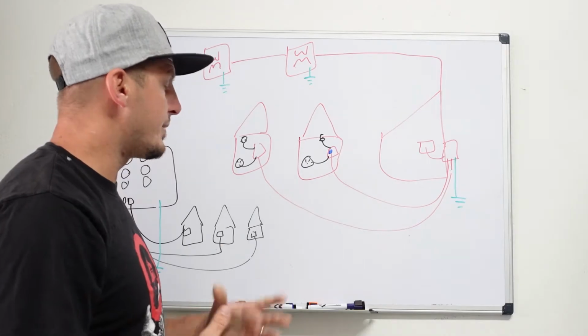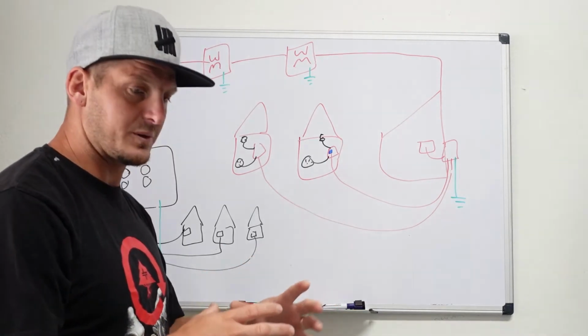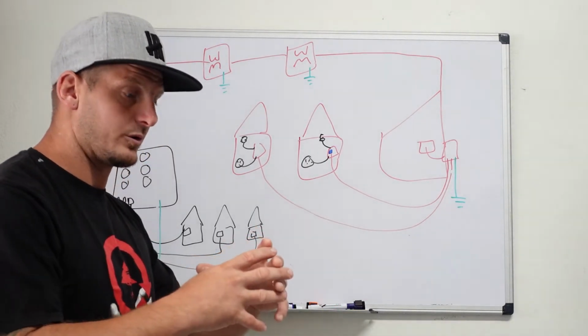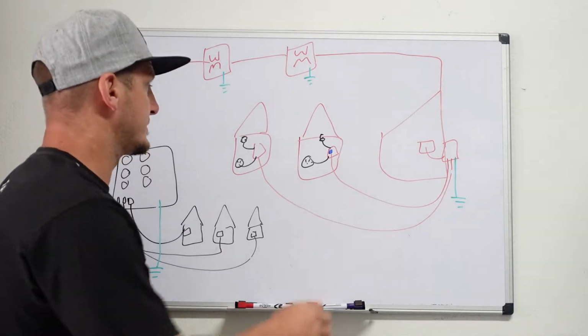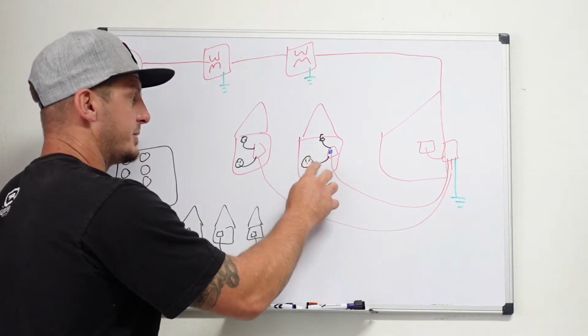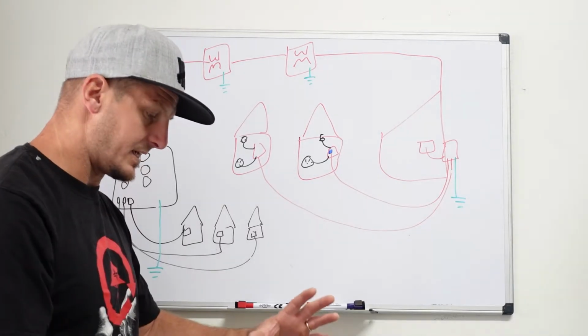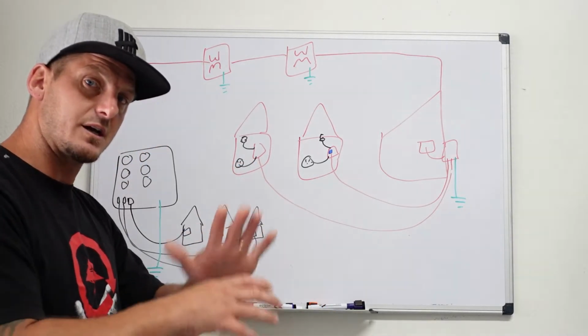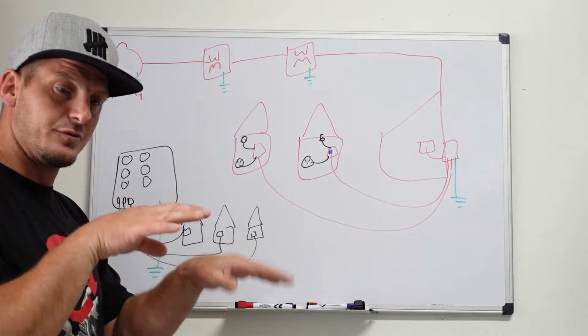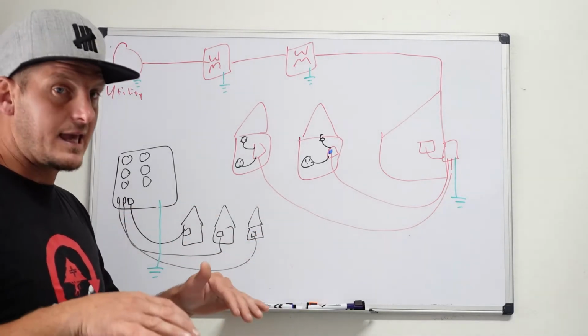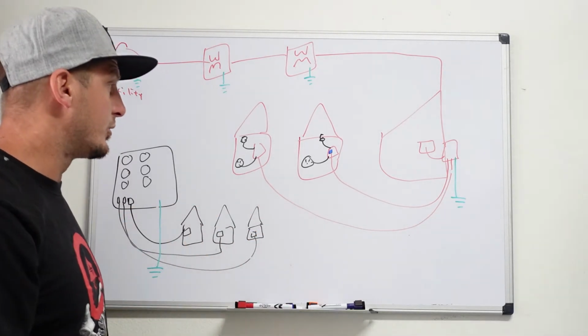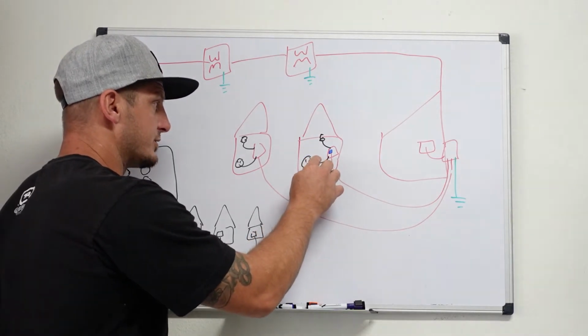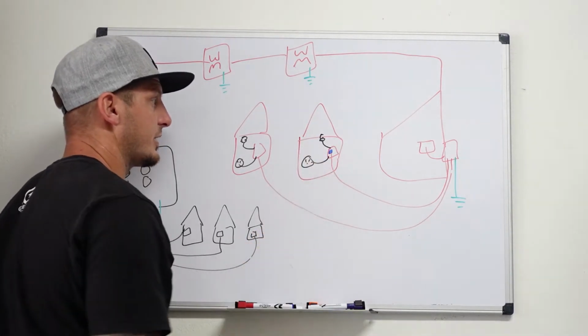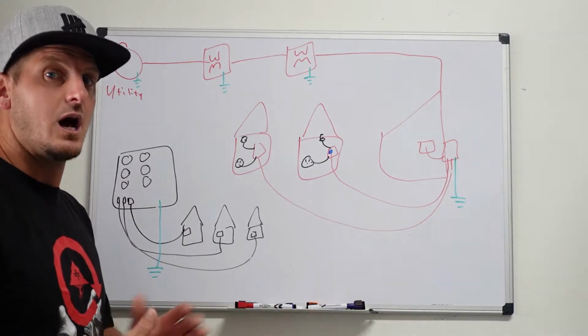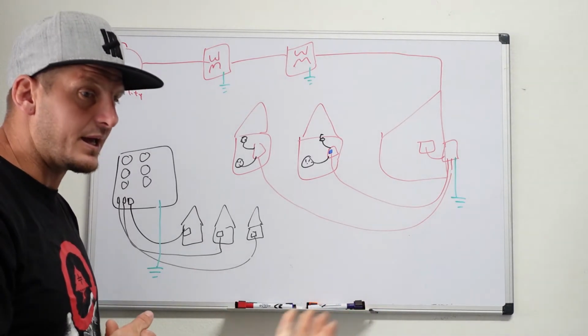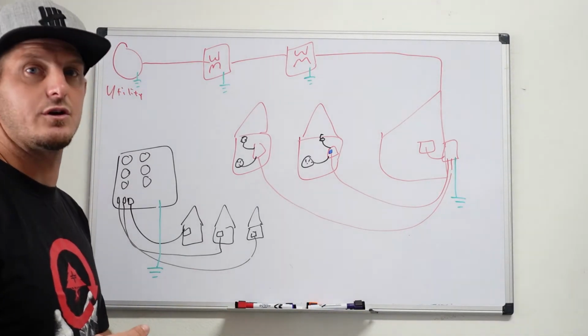The whole home surge protector is looking for a large load, so you'll also want to protect individually at each piece of sensitive equipment. If the load isn't large enough for it to catch - only a few volts different - it can pass through. So you should also put an individual surge protector at each location. Technically it covers the whole house, but not in all circumstances.